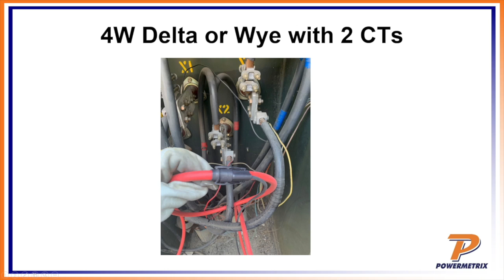Having those two probe channels on the Powermetrix equipment allows us to use two probes. You can even measure the burden on a CT. I've got MN114s or MN375s, both 10 amp rated, and you can see the connections there. That would let me come up and pick up my currents if I want to measure the burden. I just get those clamp-ons up there to measure that burden.